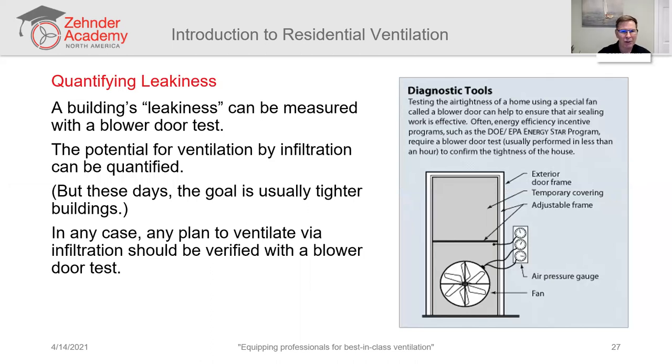Most of you are probably familiar with this, but the idea is you seal up a house, you put this blower door device over the front door opening or any door opening on the exterior wall, and then you pressurize or depressurize the house, or you actually run the test in both modes, and then you measure how much pressure it takes or how much leakage you get at a certain pressure. And that allows you to quantify the leakiness of the building, and then you can in turn try to predict with some reasonable guesstimate how much ventilation you might get through infiltration or exfiltration.